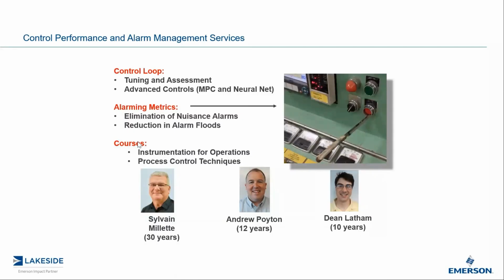Any major industrial disaster that has occurred will have roots in poor alarm management. And that picture you see there is not a Google picture. It's a real picture we took at the controls at a customer site. This is during a shutdown. They didn't want the alarm to come on all the time, so they put a steak knife in there.